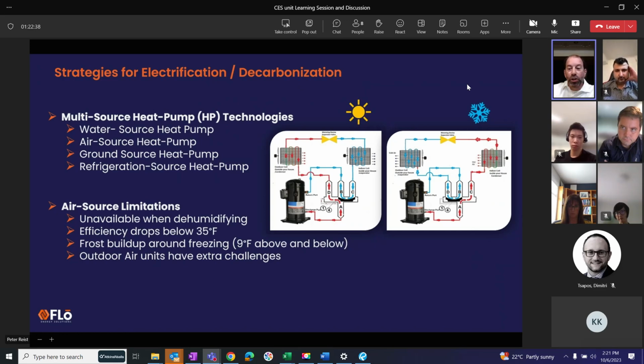So a DOAS unit that is just outside air, this question got asked of this manufacturer, they shut down at 45 degrees Fahrenheit. That's the coldest they can get, because that indoor coil has to have a relatively warm entering air temperature. So if it's recirculating, happy as punch, it's getting 75 degrees. It loves that. But as soon as you bring in outside air onto these heat pumps, they really struggle. And if it's all outside air, like a DOAS, then they actually don't qualify as heat pumps because they can't run at that 17-degree rating point.